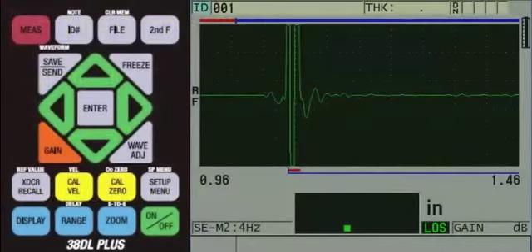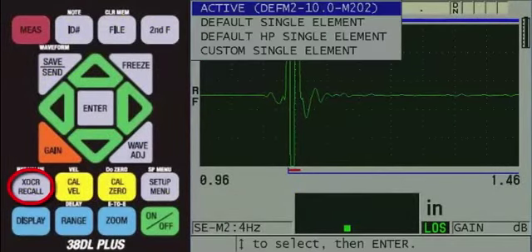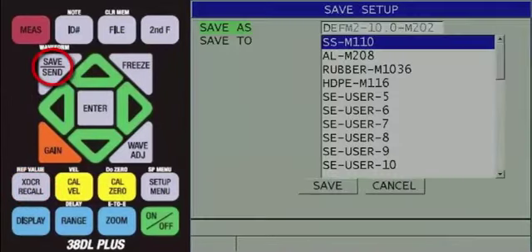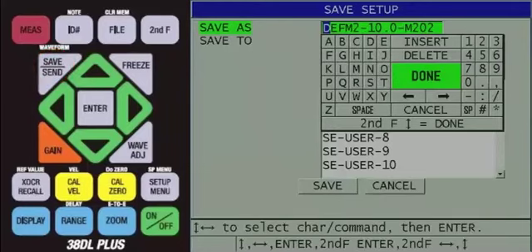After you've solved the application and calibrated the instrument, it's time to save the transducer setup. To do this, press the XDCR recall key. Now, with the active setup highlighted, press the Save/Send key. This will bring you to the Save Setup screen. Here, you will notice that Save As is highlighted and a virtual keypad appears on screen. You can now use the keypad on screen to enter in a name for the custom transducer setup.